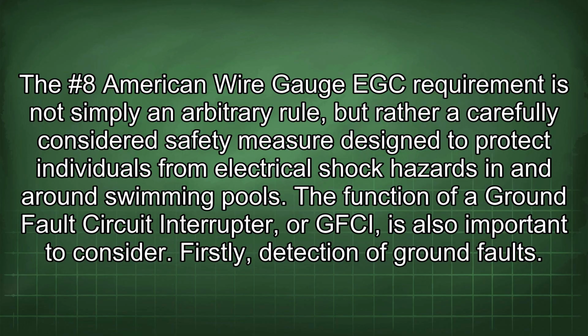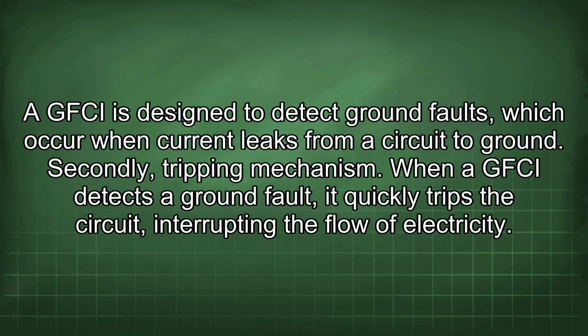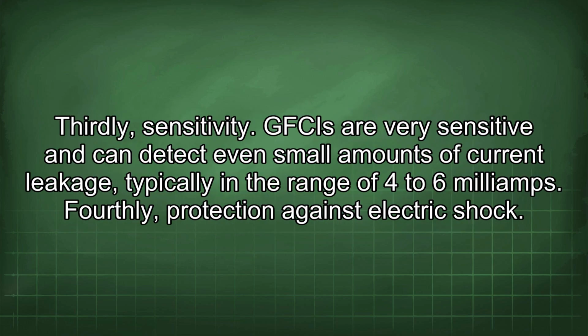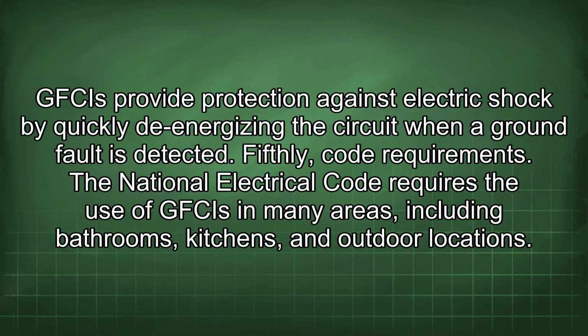The function of a ground fault circuit interrupter, or GFCI, is also important to consider. Firstly, detection of ground faults. A GFCI is designed to detect ground faults, which occur when current leaks from a circuit to ground. Secondly, tripping mechanism. When a GFCI detects a ground fault, it quickly trips the circuit, interrupting the flow of electricity. Thirdly, sensitivity. GFCIs are very sensitive and can detect even small amounts of current leakage, typically in the range of 4 to 6 milliamps. Fourthly, protection against electric shock. GFCIs provide protection against electric shock by quickly de-energizing the circuit when a ground fault is detected.